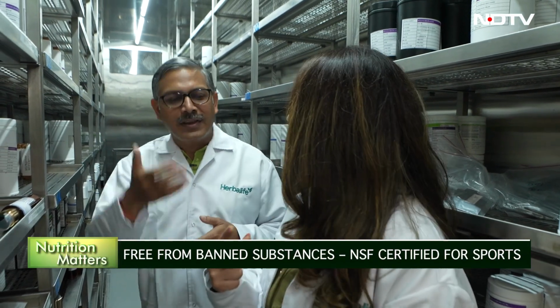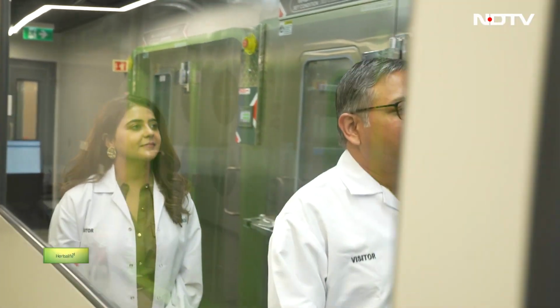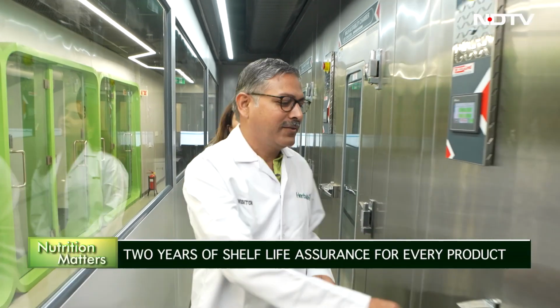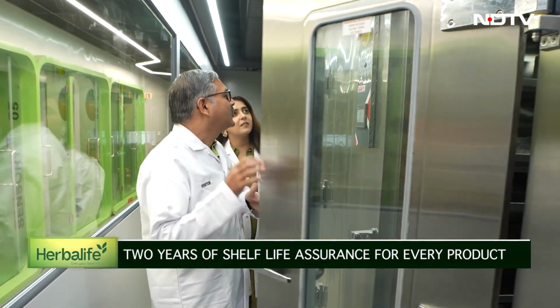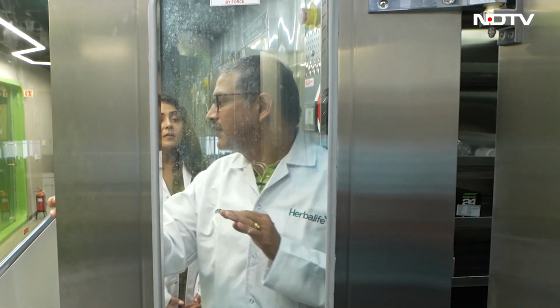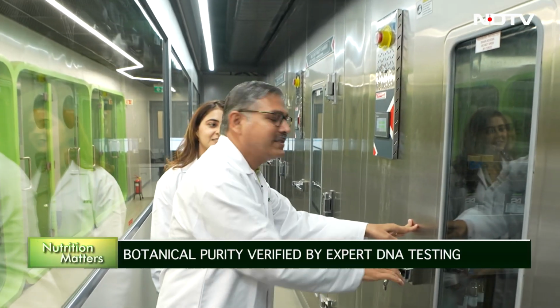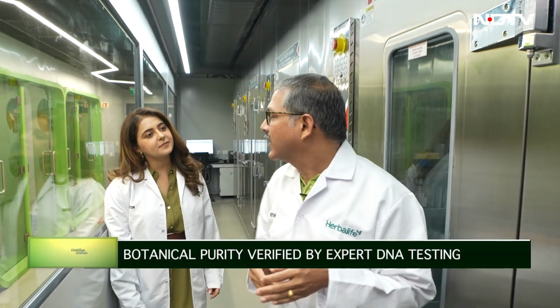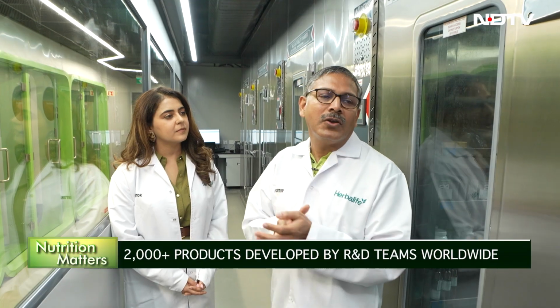Wow. Let's check it out. This is another chamber which I was explaining. It's maintained at 40 degrees and 75%. And if you go inside, you feel it. Oh my God, it's even more hot. So this chamber we are maintaining at 40 degrees centigrade and 75% humidity. Here the products are stored for 6 months, and the 6-month data will give me the shelf life extrapolation up to 24 months.